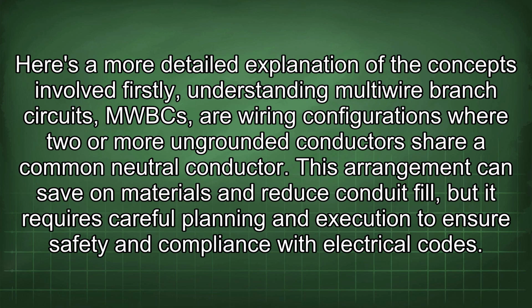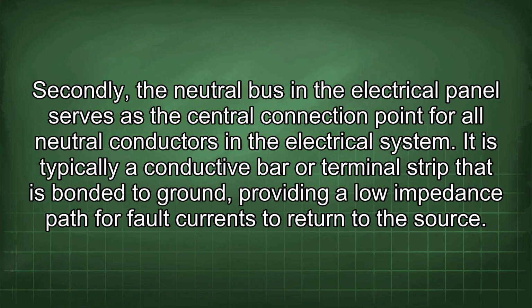Firstly, understanding multi-wire branch circuits. MWBCs are wiring configurations where two or more ungrounded conductors share a common neutral conductor. This arrangement can save on materials and reduce conduit fill, but it requires careful planning and execution to ensure safety and compliance with electrical codes. Secondly, the neutral bus in the electrical panel serves as the central connection point for all neutral conductors in the electrical system. It is typically a conductive bar or terminal strip that is bonded to ground, providing a low impedance path for fault currents to return to the source.